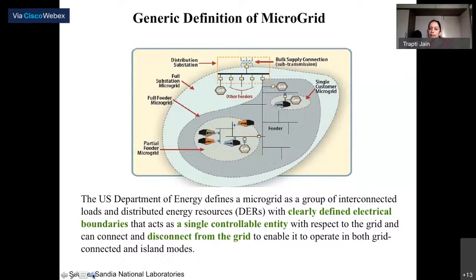With this definition, any DER installation can be called a microgrid, but there are three conditions. One, they should have clearly defined electrical boundaries. Two, they should be a single entity and able to disconnect and connect from the grid. Three, they should have power generation capacity greater than or equal to, actually greater than, the critical load which needs to be supplied in the microgrid.